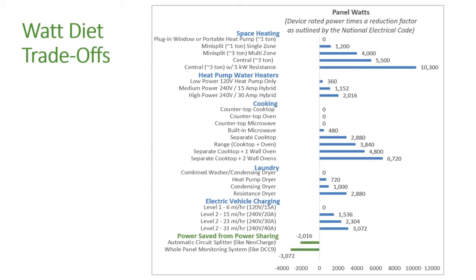Moving our way down through water heaters, we can see these upcoming new products that a bunch of us have been working on: 120 volt heat pump water heaters. They'll have a real low panel draw, about 360 watts on the panel, versus the common 30 amp version, which counts as more than 2,000 watts — it's a 4,500 watt machine, but it's only counted at 40% coincidence. Anyway, you can see the span of options available is about as wide as some of the other things on the heat pump water heaters.